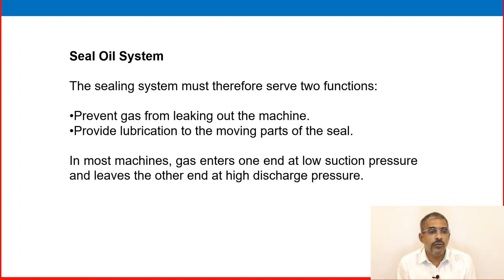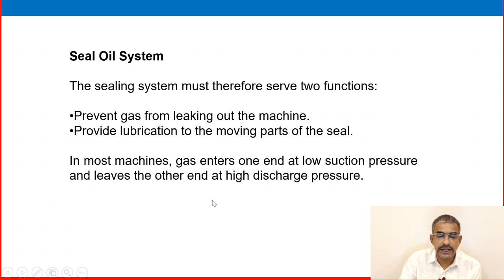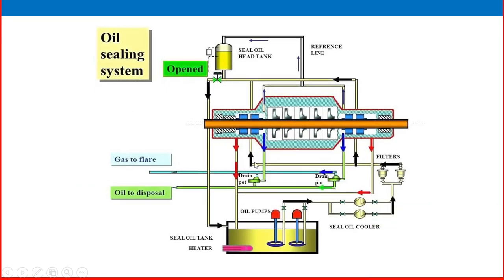Now we move to the seal oil system. The sealing system must serve two functions: prevent gas from leaking out of the machine, and provide lubrication to the moving parts of the seal. In most machines, gas enters one end at low suction pressure and leaves the other end at high discharge pressure. The seal oil system has a seal oil tank, seal oil pump, filter, and cooling system.